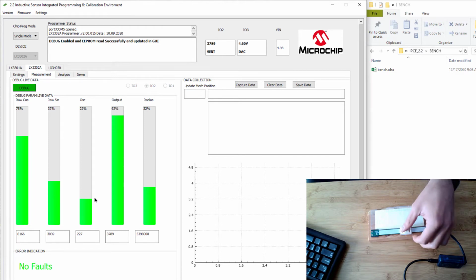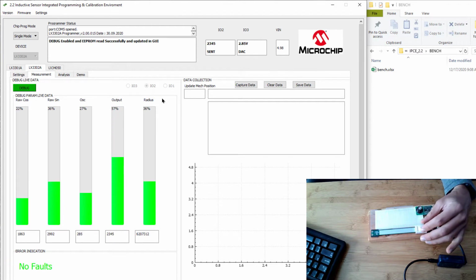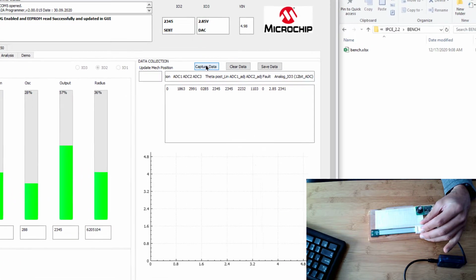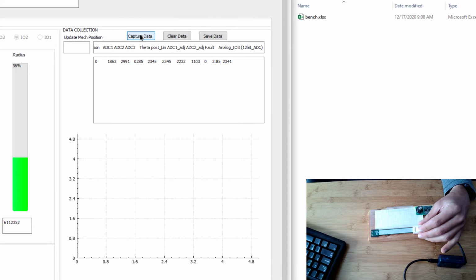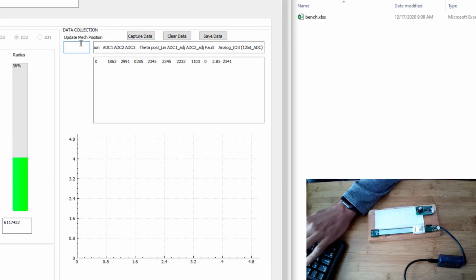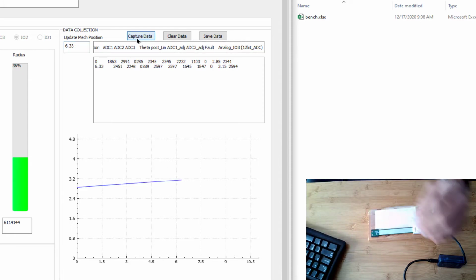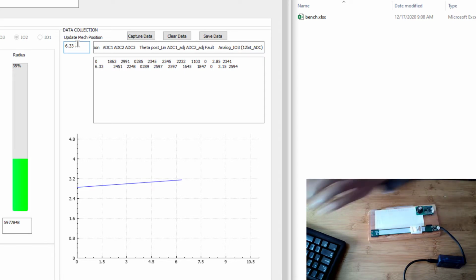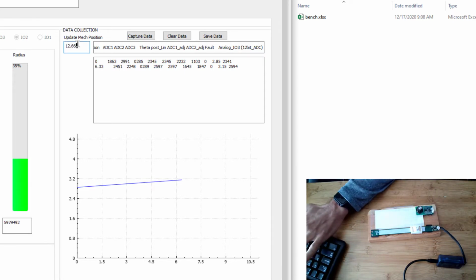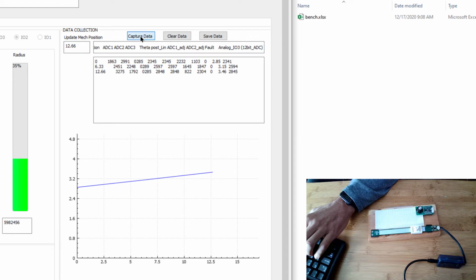With this, I'm going to move the target to the start of the measurement range, capture data, and then go to the next block on my graph paper. I'm using my graph paper to help me measure the mechanical position, which I know is 6.33, and I press the capture button again. Then I go over one more to 12.66 millimeters and hit the capture button.